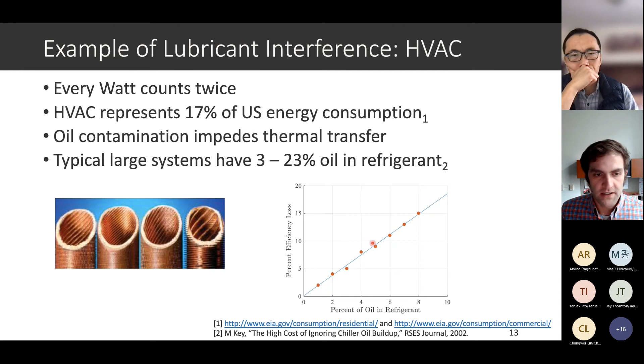Trane did a study on this, and they showed on this plot how the percent of oil in the refrigerant contributes to overall efficiency loss in the entire building. And you can see that if we're sitting at about 4% oil in our refrigerant, that corresponds to a 7 or 8% reduction in entire building HVAC efficiency. And these large systems are on the order of megawatts, right? So this is a very large amount of kilowatts just lost due to oil being in the pipes.